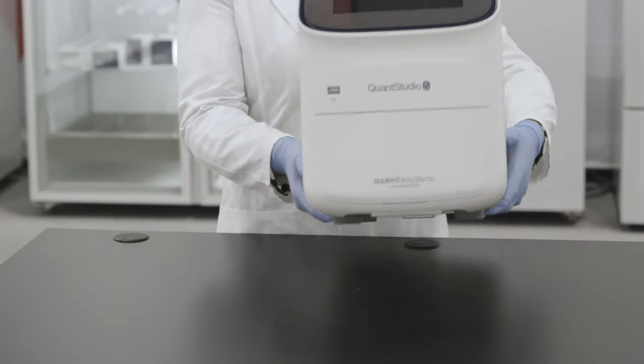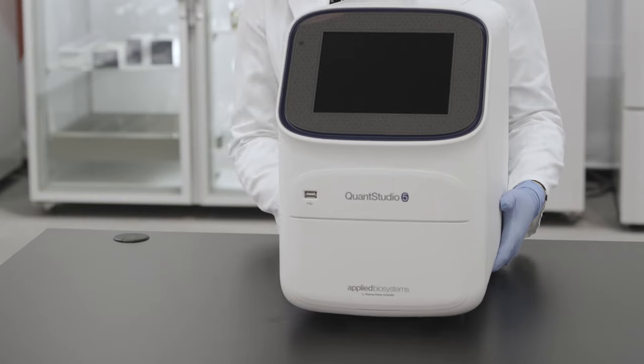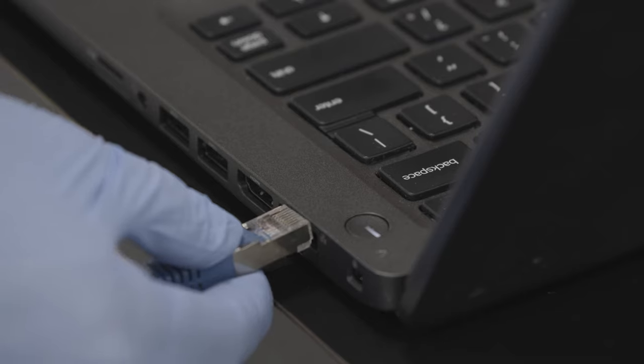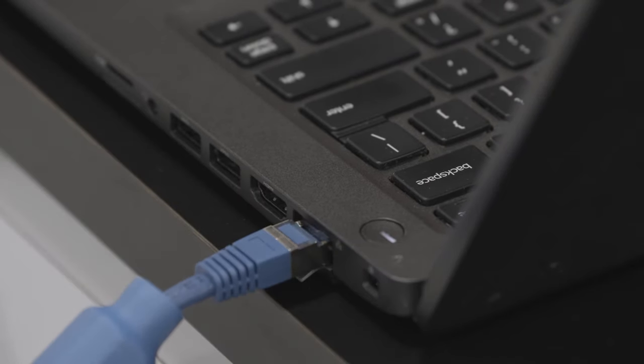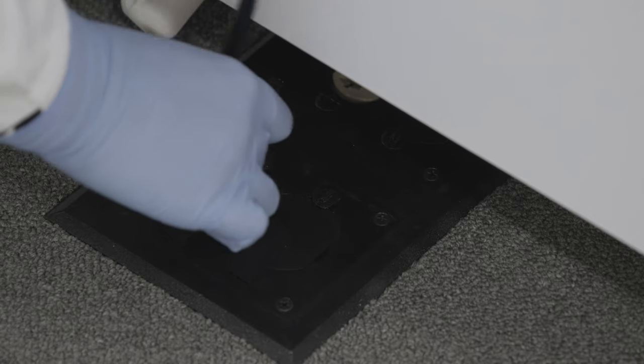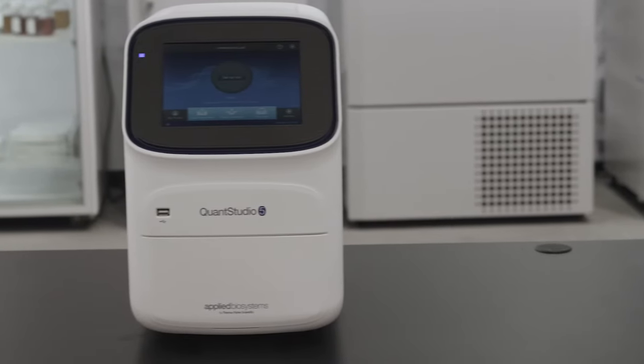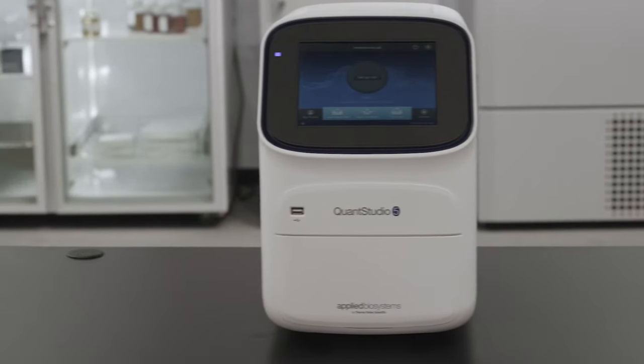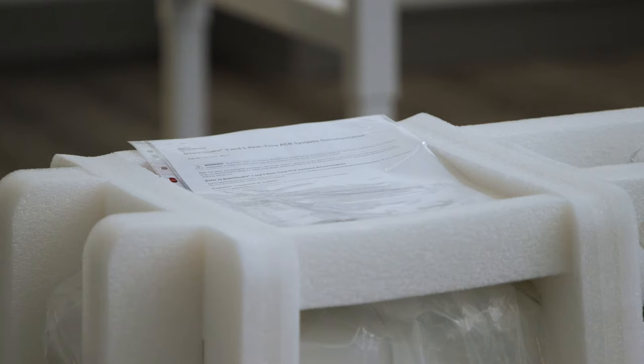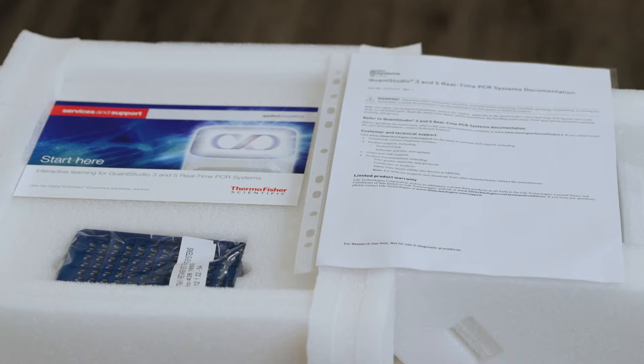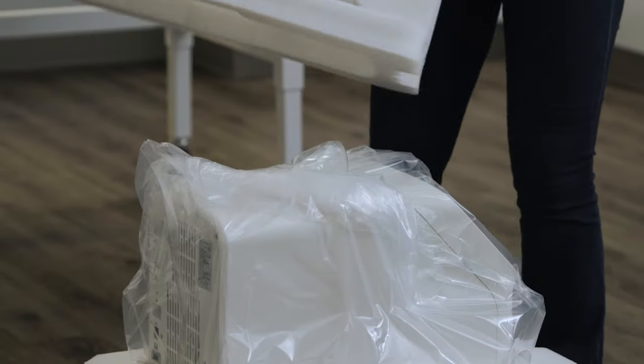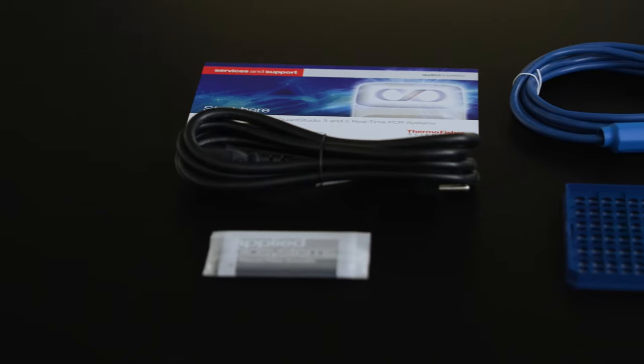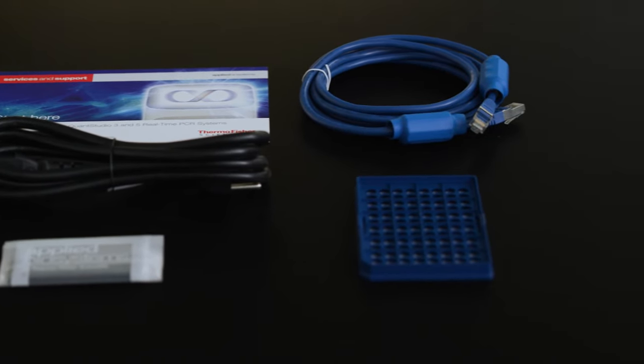Next, ensure that you have the correct installation materials, including personal protective equipment, a network connection if needed, and a power outlet. Be sure there is ample space behind the instrument to access as needed during installation. Follow the pre-printed instructions on the instrument box to unpack the instrument. The instrument box should contain reference documentation, the instrument, and the accessories needed to power and run the instrument.